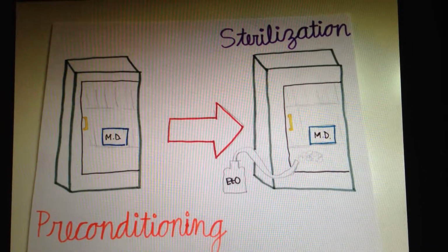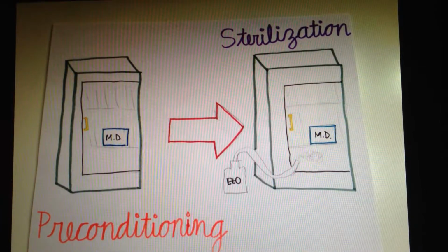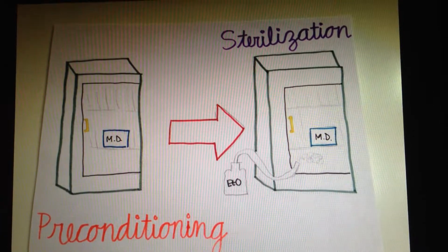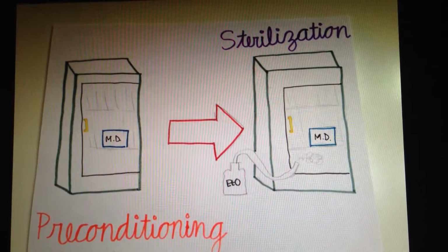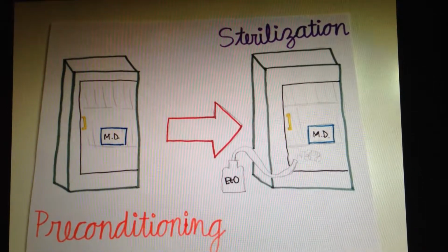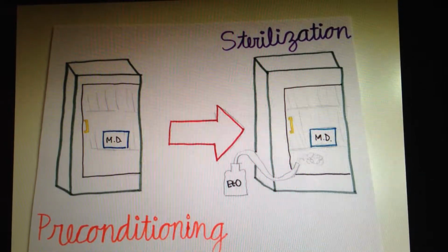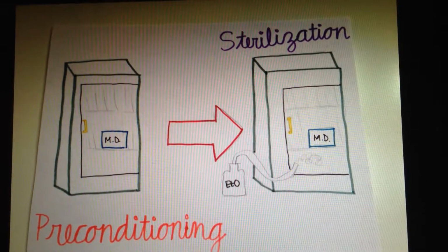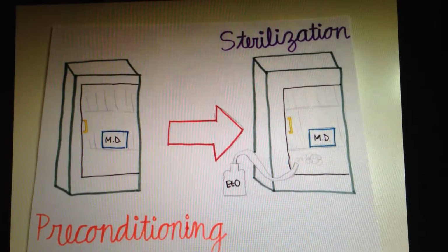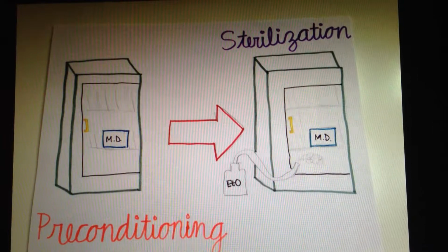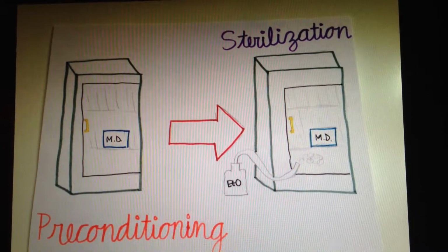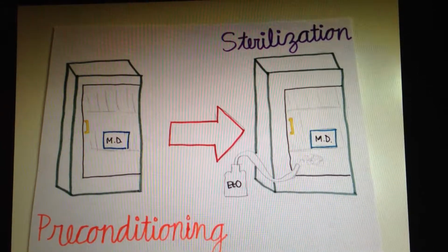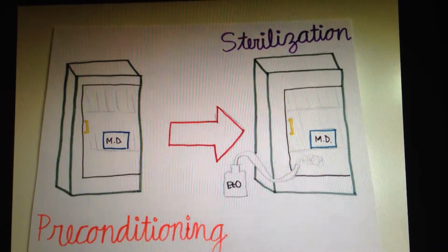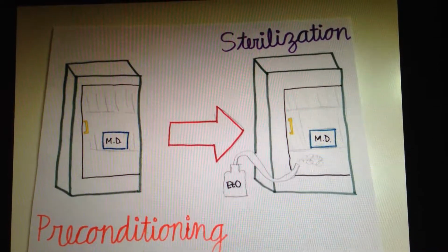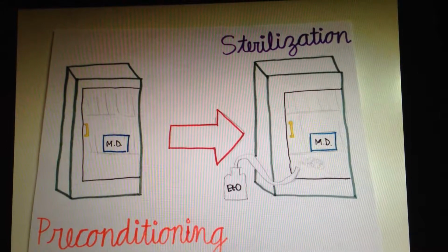Once that is finished, you will evacuate the gas. Once it has reacted, evacuate, not evaluate, and then air will be re-admitted back into the system. The final step, which is aeration, is probably the most important and longest part of the ethylene oxide sterilization cycle. This process can take up to several hours to several weeks.